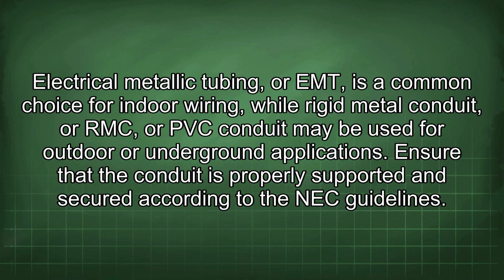Electrical metallic tubing, or EMT, is a common choice for indoor wiring, while rigid metal conduit, or RMC, or PVC conduit may be used for outdoor or underground applications. Ensure that the conduit is properly supported and secured according to the NEC guidelines.